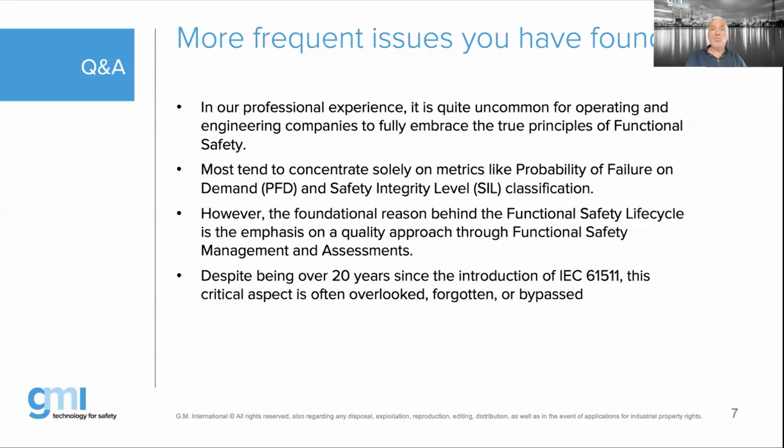That's the same as you do on your instruments. When you have a PFD, when you have a SIL, you estimate when that device will not work when you need it. The problem is, the moment an engineer sees the number on paper, they start to believe it, or they start to dream it. Well, stop dreaming, stop blindly focusing on PFD. It's nothing more than an estimate.